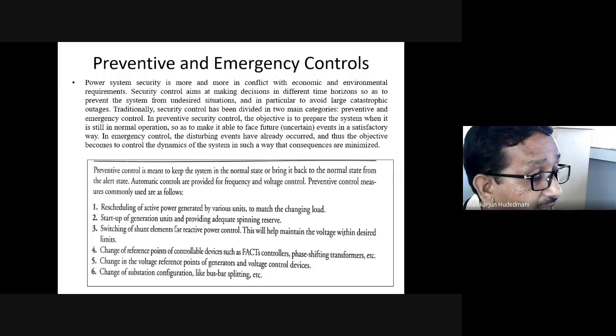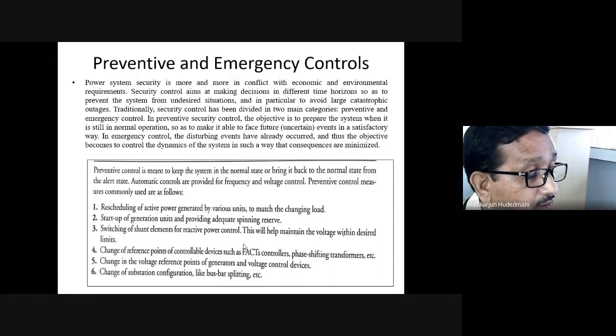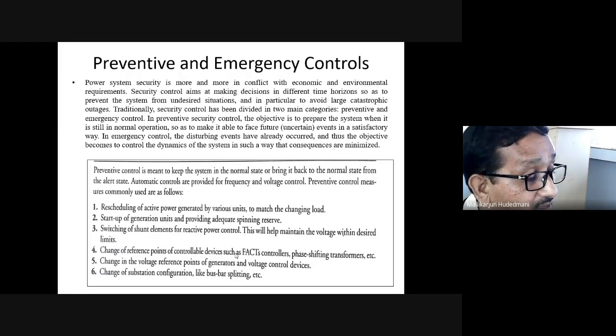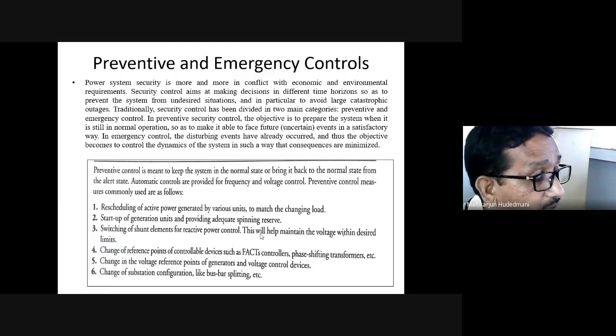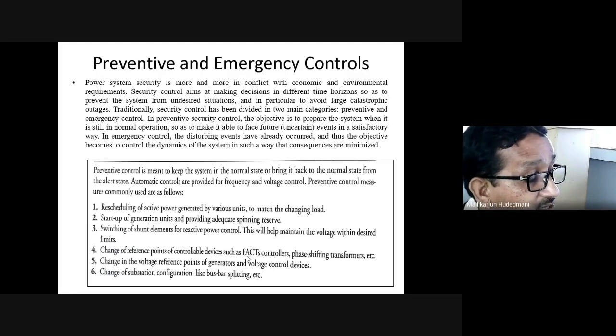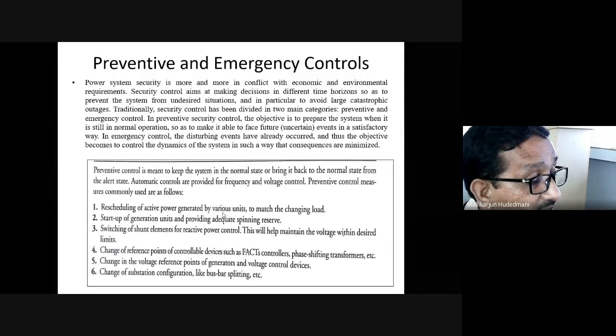Change of reference point of controllable devices such as flexible AC transmission mechanism. FACTS devices, which is nothing but for the reactive power and voltage control, the power electronic substitute is FACTS. Flexible AC Transmission System, flexible AC transmission system controller. So these provide sufficient active and reactive power supplements as required. Basically, these are meant for reactive power and voltage, which will be in system to support the requirements of active and reactive power balance. So these must be tuned properly, adjusted such that their action on the power system and the elements which are interconnected balance the requirement appropriately.